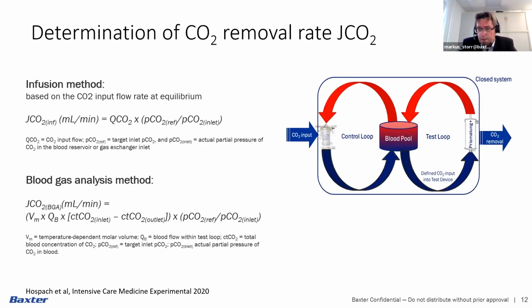So to determine the CO2 removal rate of the test device, the CO2 inlet flow was adjusted to maintain the target PCO2 and to reach steady state conditions. At steady state conditions, the CO2 removal from the test circuit is exactly balanced by the CO2 addition to the control loop, since we have a closed system. That means that we can determine the CO2 removal rate of the test device by measuring the CO2 inflow rate in the loop. So the CO2 feed into the system equals, so to speak, the amount removed from the system.